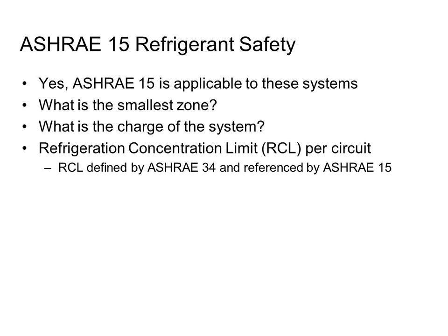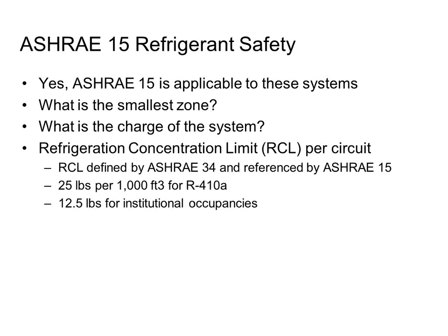In the case of a VRF system, my 2 condensing units outside and my 10 evaporators inside is going to be 1 circuit. For R410A, which is what most VRF manufacturers use in the United States, I'm allowed to have 25 pounds for every 1,000 cubic feet. I'm just going to point out that's cubic feet, not square feet. So you have to multiply the square feet by the height, for you guys that are math whizzes. So 25 pounds for every 1,000 cubic feet can leak into one particular space. So who's my smallest zone?